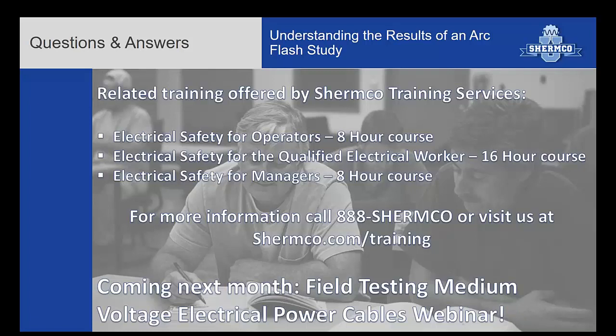And Mark, as you and I both know, in NFPA 70E, Article 130, work involving electrical hazards, they do specifically talk about two methodologies of determining your risk. One would be if an incident energy analysis study or an arc flash study was done, you would have the labels or the stickers present. But the other is that 70E also provides tables where you can do calculations for selection of PPE. It's a little bit more extensive. You need to try to find your maximum fault currents, your clearing times, etc.